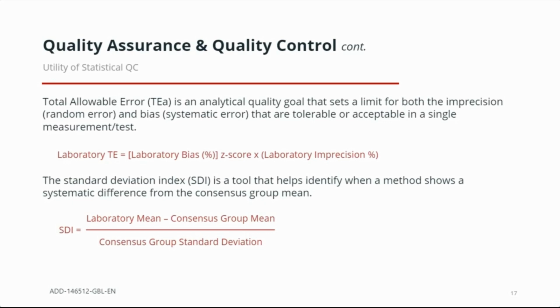The standard deviation index is another tool that helps us identify a systematic difference from the peer group mean. The SDI looks at lab mean minus group mean divided by the group standard deviation, where an SDI of 0 indicates there's no difference between the laboratory mean and the consensus group mean. This is a favorable condition in that bias is 0. An SDI closer to 2.0 would indicate a significant difference from that peer group mean and would warrant some review.